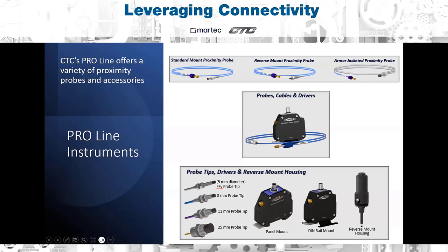This 5 millimeter and 8 millimeter probe tip will have a measurement range of about 2 millimeters. This 11 millimeter probe tip will have a measurement range of 4 millimeters. And this 25 millimeter probe tip, which is really only used in special applications for very large turbines, will have a measurement range of all the way up to 13 millimeters.